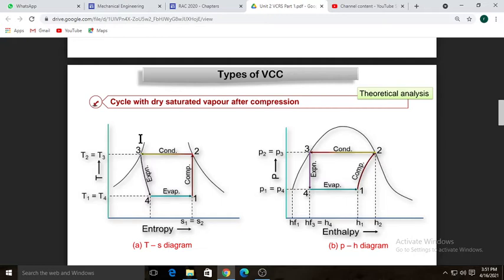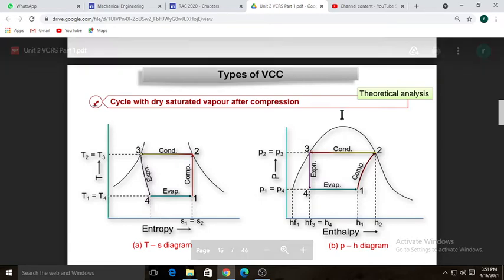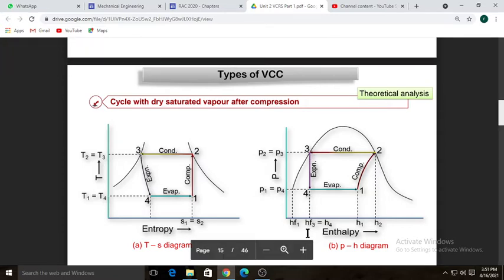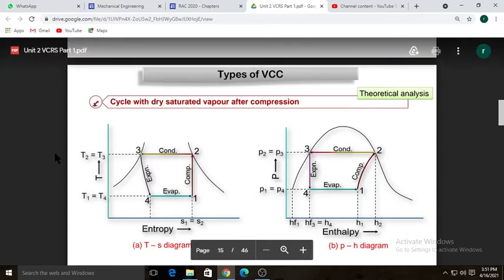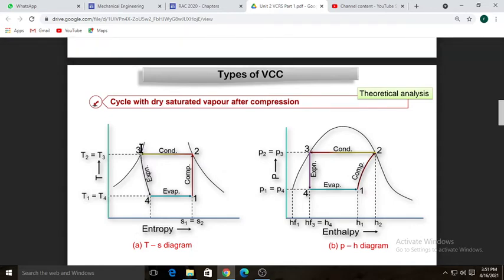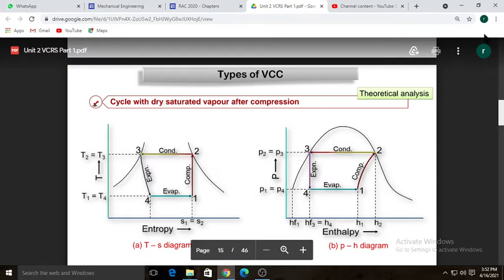Process three-to-four is expansion through a nozzle or expansion valve — an isenthalpic process, so enthalpy remains constant. However, on the TS diagram, as pressure decreases, a flash effect occurs: some vapors get evaporated, entropy of the liquid increases, and the graph line is slightly curved. Process four-to-one is evaporation, which produces the refrigerating effect.